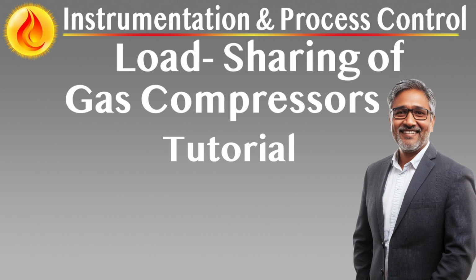Anti-surge controller coordination. Each controller receives periodic data from all other anti-surge controllers in the same compressor train. The controller identifies the maximum recycle valve output currently active. Based on whether the surge condition is improving or worsening, each unit modifies its valve modulation rate: accelerated closure when moving away from surge, synchronized opening when surge risk increases.